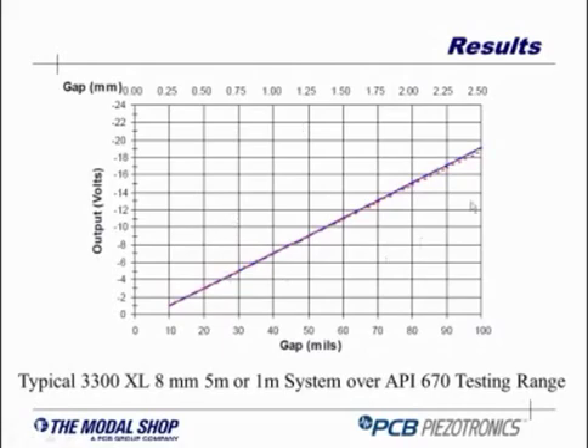If you look at this line, you expect to see about 200 millivolts per mil type of output. Your customer needs to do that type of testing for every prox probe installed on the machine.